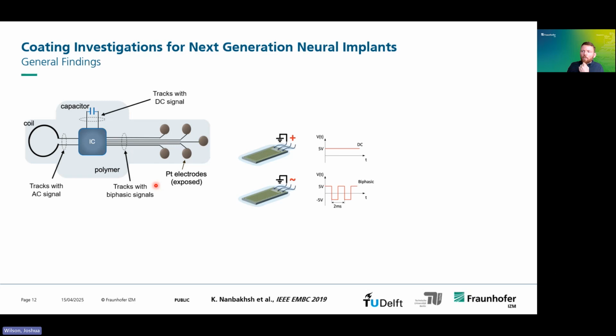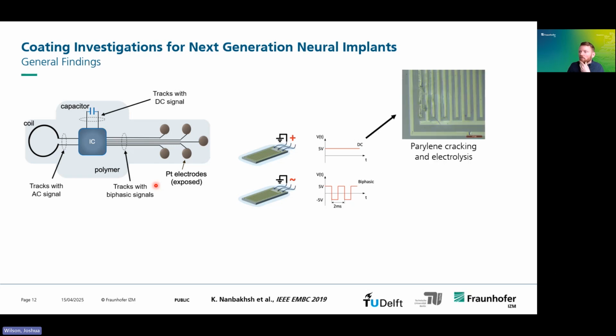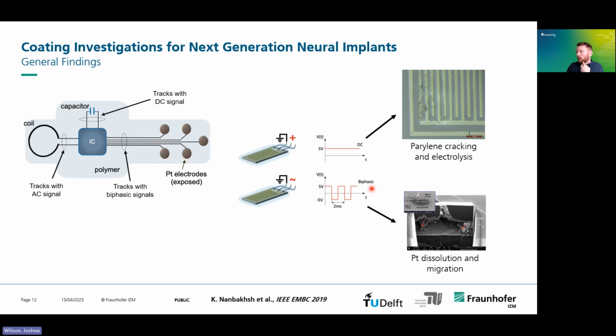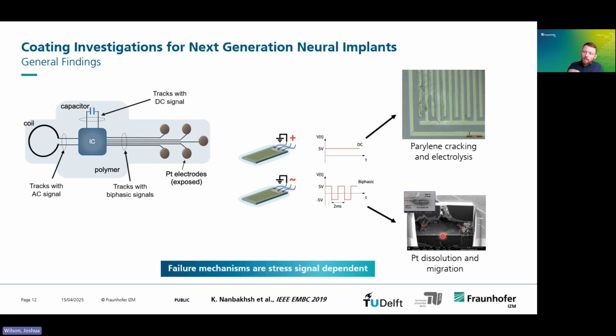So what we investigated was what happens if we use different signals on our test structures. Will the results be the same? And in fact, the answer is no. In one case where we applied DC, we saw cracking of the coating. And in another case where we applied a biphasic signal, we saw the metal dissolving, corroding, migrating. So what this tells us is the failure mechanism of the device is also dependent on the stress signal. Whichever signals you have in your device are going to affect the failure.